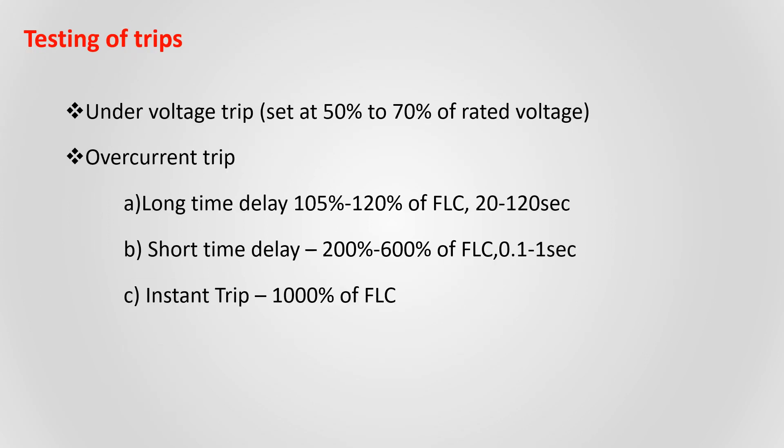Testing of trips: Undervoltage trip, or another name is no-volt coil, set at 50-70% of rated voltage. When voltage drops below the set value of UVT setting, then the UVT coil trips the breaker. It also prevents the circuit breaker from being closed when the generator is producing low voltage or zero voltage.